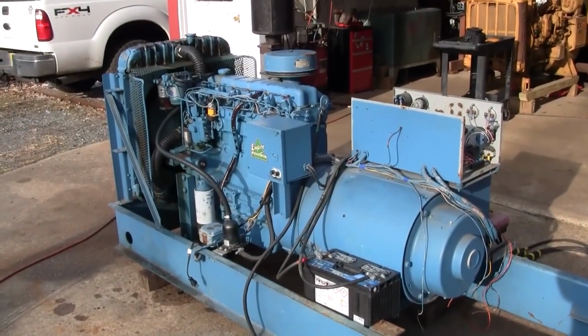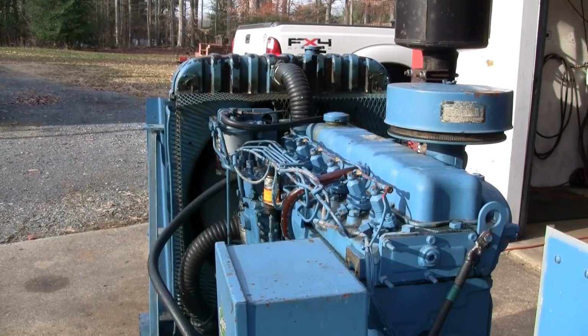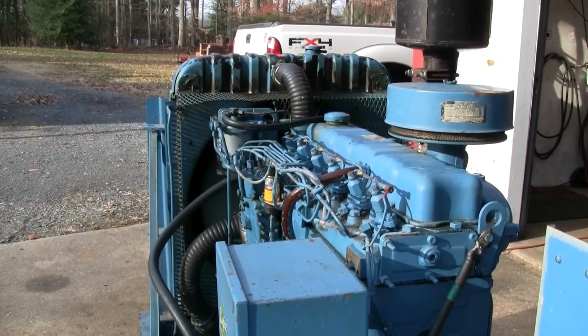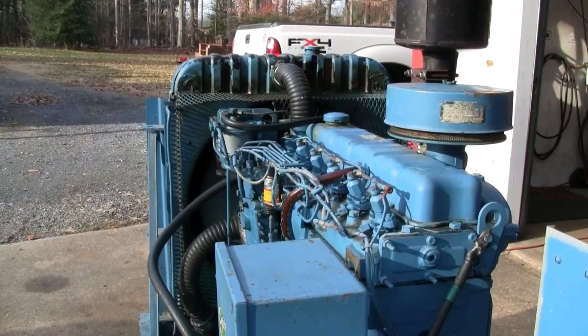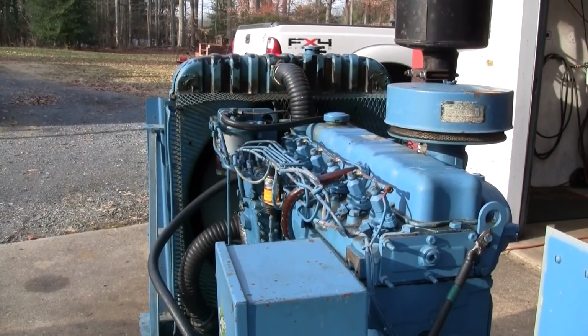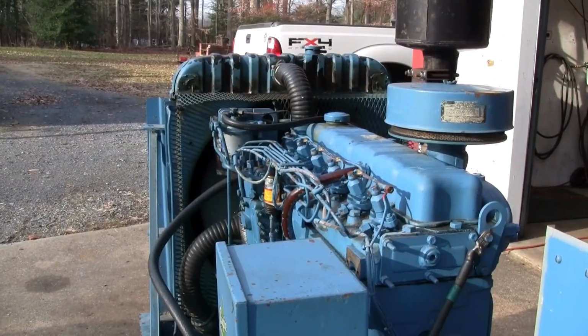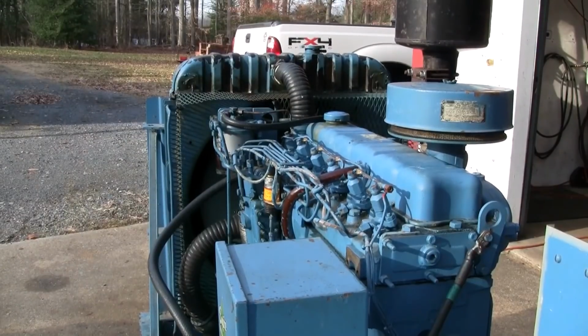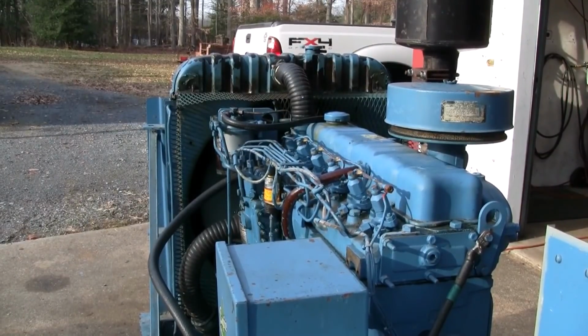I'm going to set the tripod up and increase the load. Okay, I've got you set up looking down the length of the engine. I really don't know if the camera's going to be able to pick this up. Right now we're at 22 kilowatts worth of load. I'm going to drop that load off, and then I'm going to reapply it. Can you see that shudder that the engine has? Let me increase the load. Now we're at 32 or 33 kilowatts.